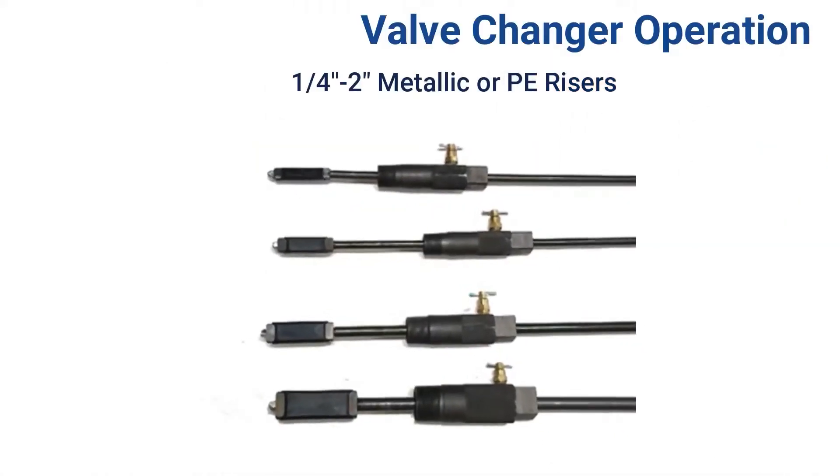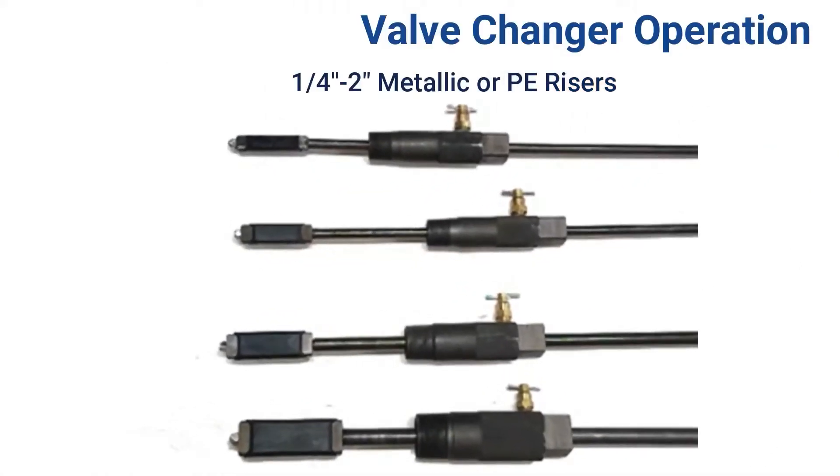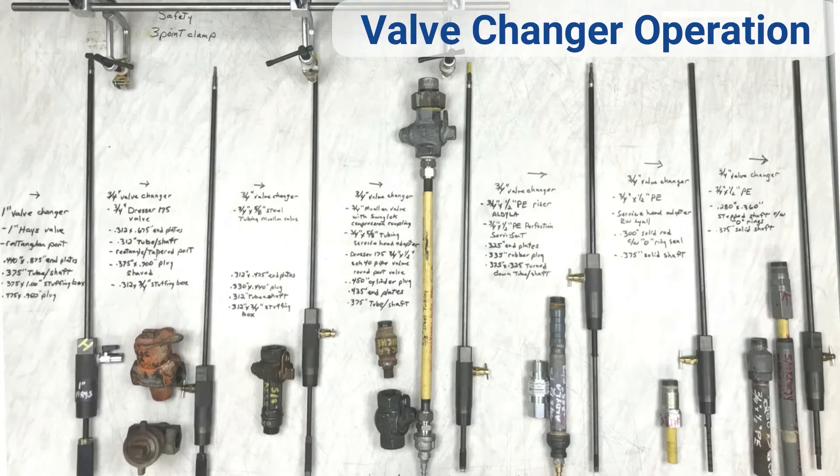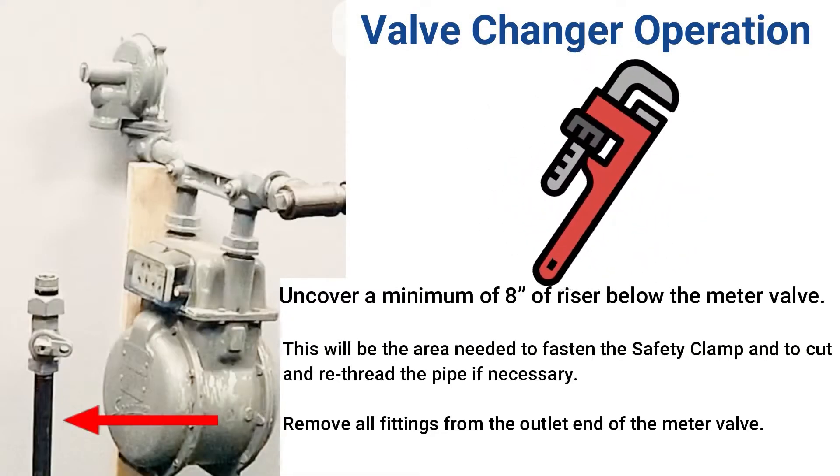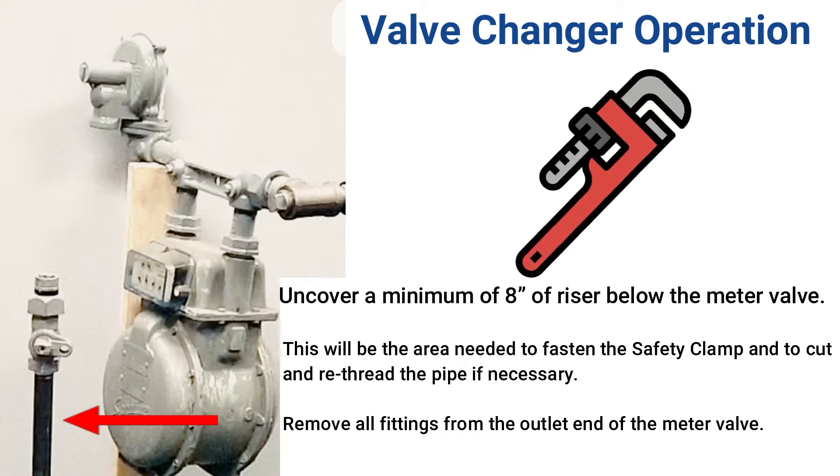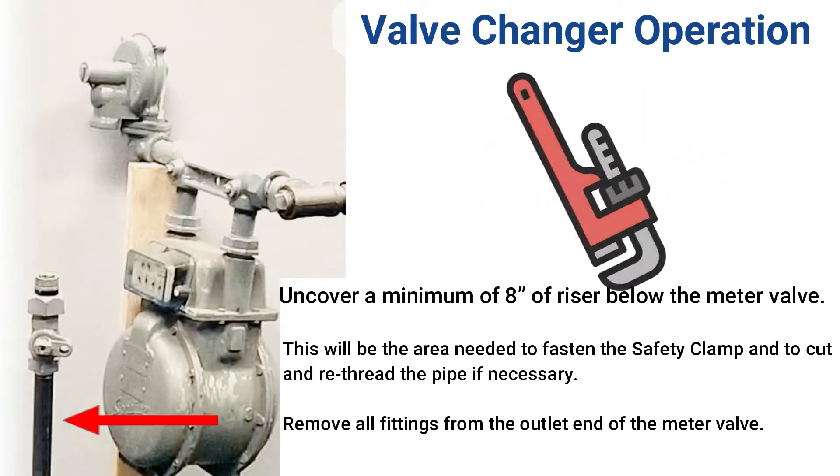To begin, select the proper size valve changer according to the size of the meter valve to be removed. Close the meter valve and remove necessary piping to gain access to the valve and purge the gas out of the meter assembly according to company procedures.